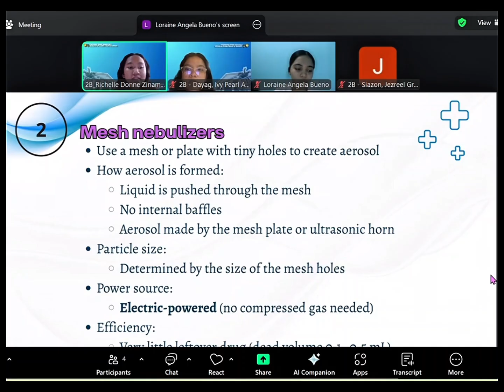The next type is the mesh nebulizers. They use a mesh or plate with tiny holes to create aerosol. Sorry. So how is aerosol formed? The liquid is pushed through the mesh, no internal baffles, and aerosol is made by the mesh plate or ultrasonic horn. The particle size is determined depending on the size of the mesh hole, and its power source is electric power. And last, its efficiency is that it has very little leftover drug with a dead volume of 0.1 to 0.5 ml. And another efficiency, it is highly efficient, especially for drug delivery.